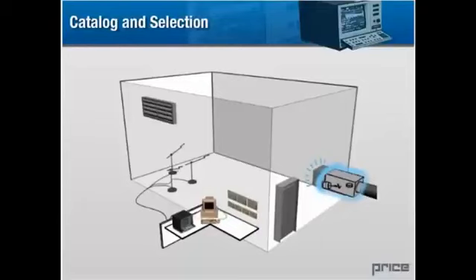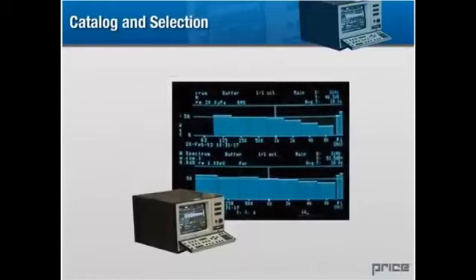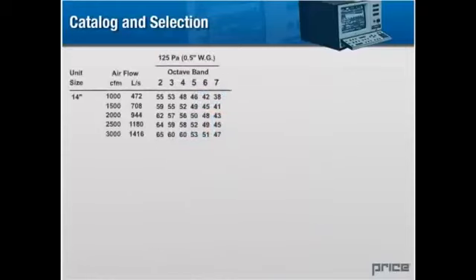Most devices are tested by passing air through the device at various predetermined rates and pressures. The sound produced is picked up by the microphones and fed into the Brüel and Kjaer real-time frequency analyzer to be split up into octave bands. We determine the sound power produced by the terminal unit in each of the octave bands and publish the information in a format similar to that shown. We determine sound power ratings under a variety of airflow and pressure conditions.